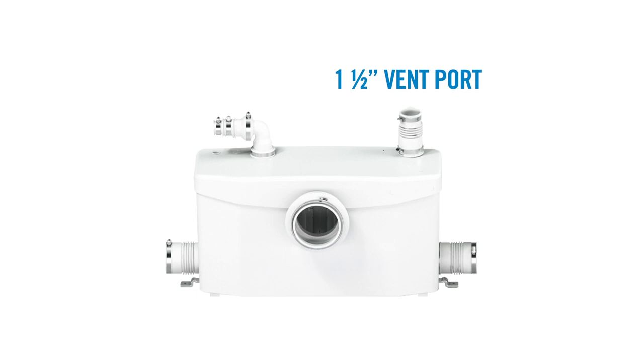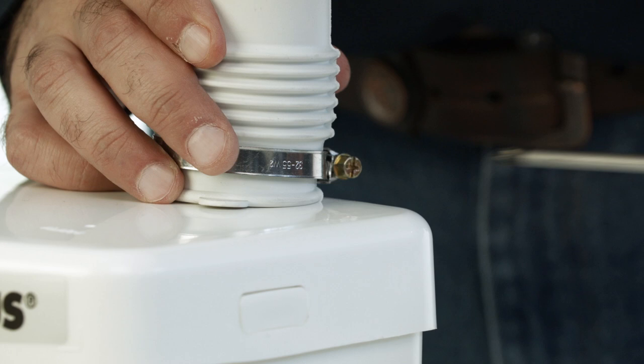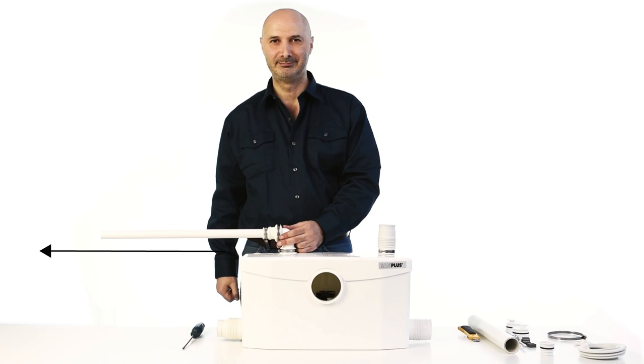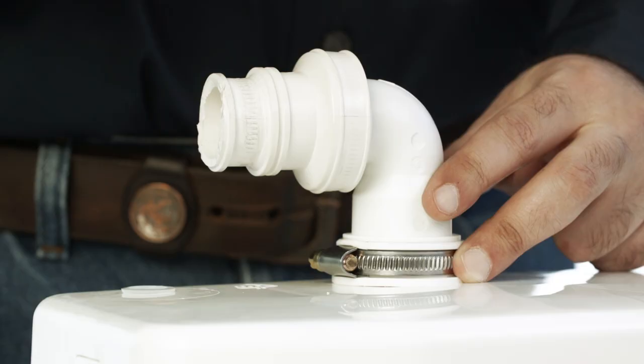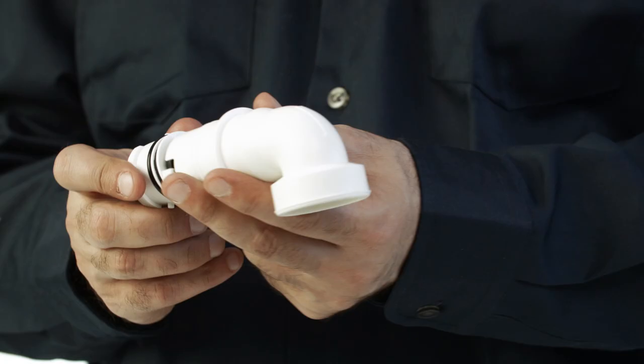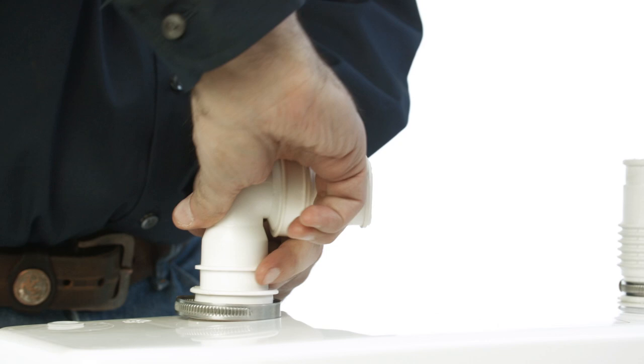Now let's take a closer look at the function of each of these connections. The 1.5-inch vent port is located at the top of the lid where the vent pipe can be installed using the rubber coupling provided. The unit discharges the waste through a 3/4-inch or 1-inch rigid pipe using the discharge elbow provided. Its built-in non-return valve prevents wastewater from re-entering the pump through the discharge elbow once the system is turned off. This elbow can also be rotated 360 degrees depending on the installation.